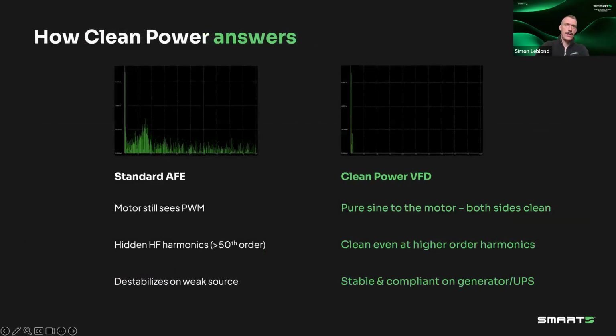And here's where the Clean Power VFD topology shines, because we address all of them. From the motor side, there are no harmonics, no dV/dt, and no common mode bearing currents, because the motor sees a pure sine wave directly. So both sides are clean, the grid and the motor. You don't have these higher order harmonics either, so there's nothing hidden, and you're already compliant with future revisions of IEEE 519, so you don't need to worry about that. And finally, you don't get destabilized by a weak source, such as a generator or a UPS.